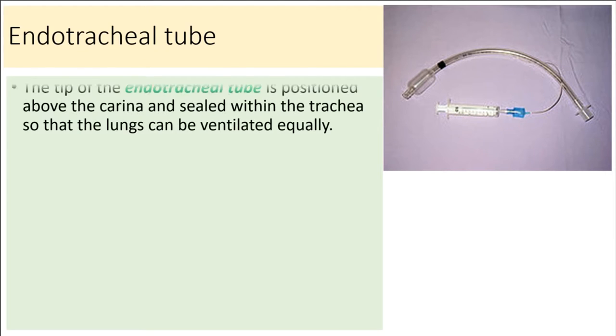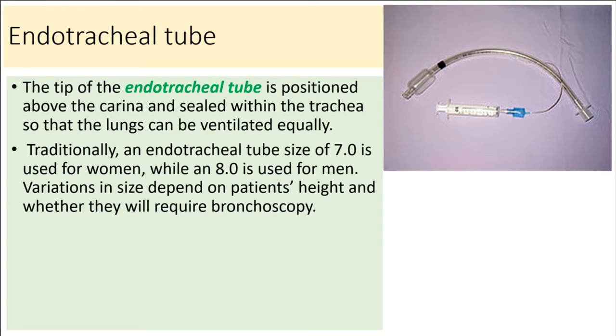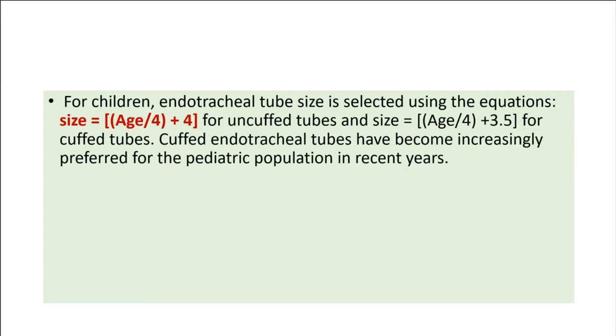The tip of the endotracheal tube is positioned above the carina and sealed within the trachea so that the lungs can be ventilated. Traditionally, an endotracheal tube size of 7.0 is used for women, while an 8.0 is used for men. Variations in size depend on the patient's height and whether bronchoscopy will be required, which needs at least a 7.5 or 8.0 tube. For children, endotracheal tube size is selected using the equations: size equals age divided by 4 plus 4 for uncuffed tubes, and size equals age divided by 4 plus 3.5 for cuffed tubes.